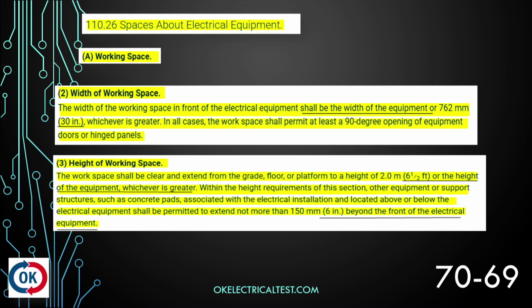Let's say I have a 24-inch piece of equipment. 24 or 30, which one's bigger? 30. So the width in front of a 24-inch piece of equipment is going to be 30 inches. Now let's say I had 48-inch wide equipment. How wide do I need to be? Which one's bigger, 48 or 30? 48. It needs to be 48 wide. So it's 30 inches or the width of the equipment, whichever is greater.